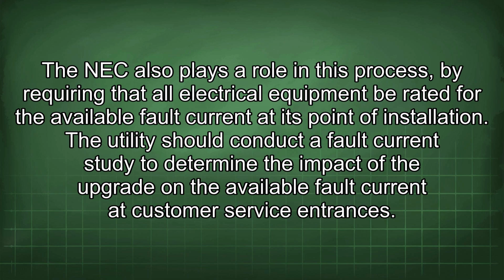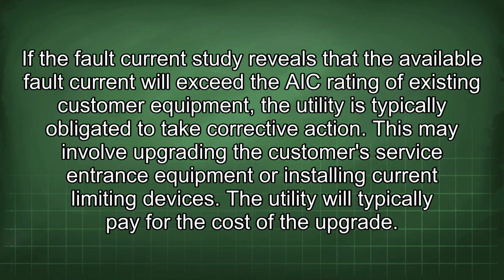The utility should conduct a fault current study to determine the impact of the upgrade on the available fault current at customer service entrances. If the fault current study reveals that the available fault current will exceed the AIC rating of existing customer equipment, the utility is typically obligated to take corrective action. This may involve upgrading the customer's service entrance equipment or installing current limiting devices. The utility will typically pay for the cost of the upgrade.